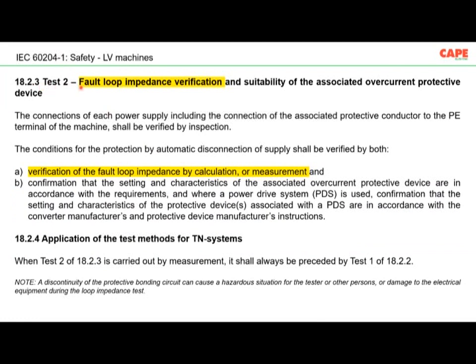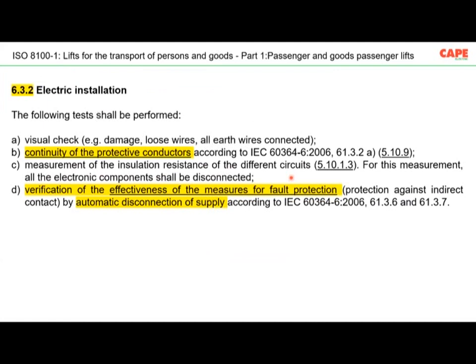Then the test number two, fault loop impedance verification. Verification of the fault loop impedance by calculation or measurement. You forget about calculation, which will be very, very difficult. At the moment, a lot of meters are there. We also do calculation. However, meters are there. After installing the machine, you are supposed to do a measurement. So basically, testing of the machine means you are supposed to test the continuity of the wire and the fault loop impedance.